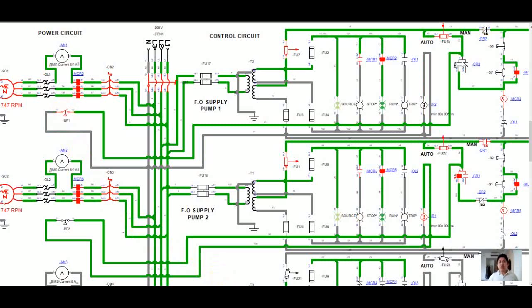As you can see, fuel oil supply pump number one is still running, but the backup or standby fuel oil supply pump number two is now also running. Since pump number one lost its pressure to supply fuel to the engine, fuel oil supply pump number two automatically started to compensate the pressure in order to maintain normal pressure and supply fuel to the engine.